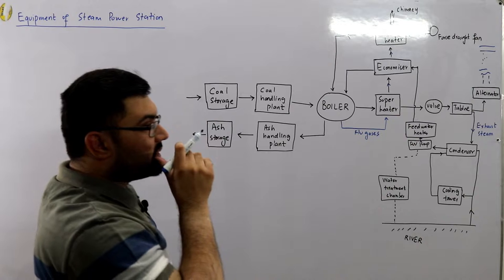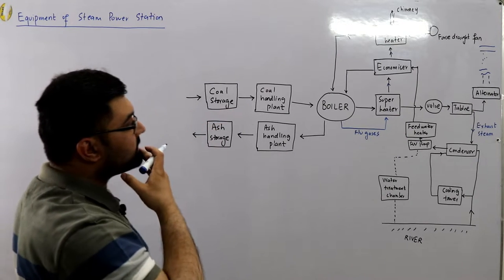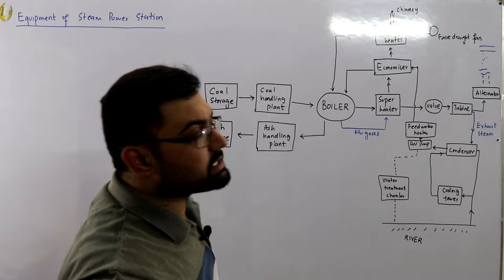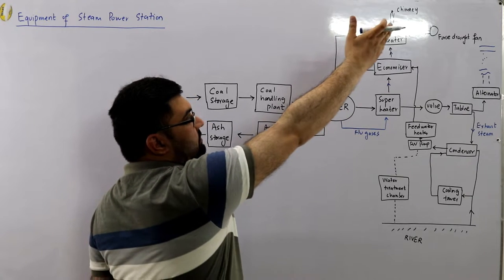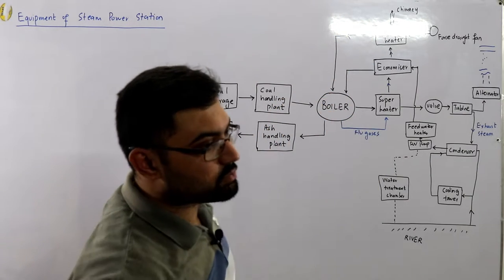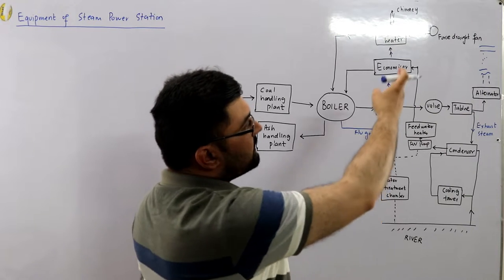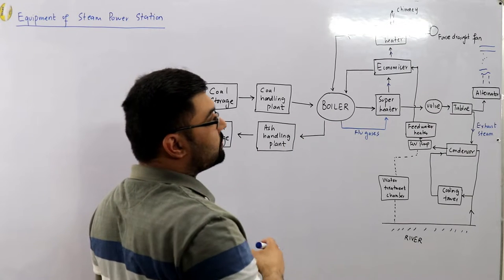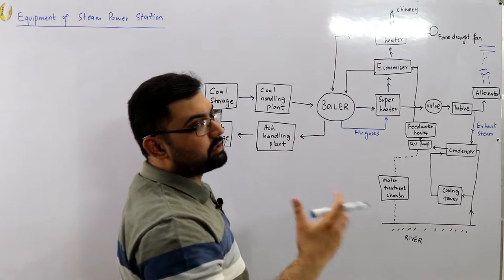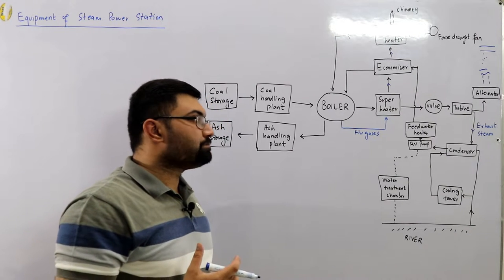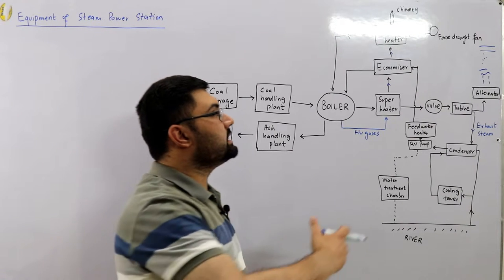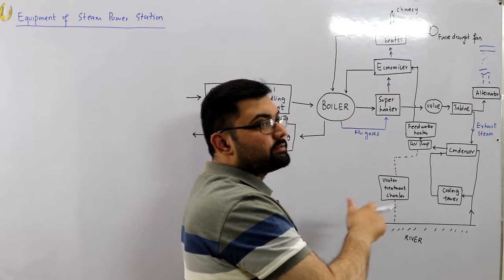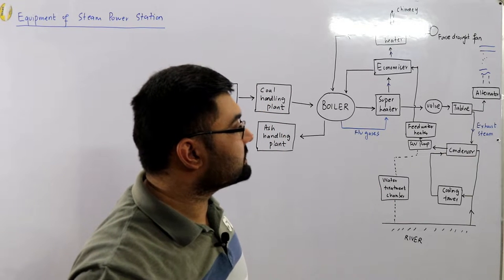The whole setup works as follows: coal is stored in the coal storage, then given to the coal handling plant where it is crushed into small pieces. In the furnace it is combusted with oxygen, which is provided via the air preheater — the air preheater heats the air by extracting heat from the flue gases formed during combustion. The boiler converts water into steam; the superheater further elevates the steam temperature. The flue gases also pass through the economizer, which extracts further heat.